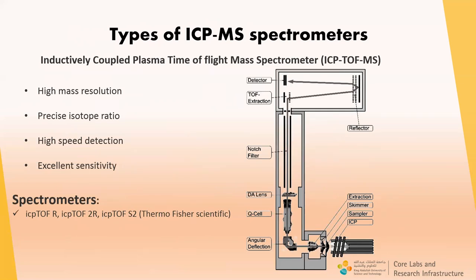Let me say a few words about inductively coupled plasma time-of-flight mass spectrometry. In the time-of-flight mass analyzer, the ion's mass-to-charge ratio is determined via a time-of-flight measurement. Ions are accelerated by an electric field so that all ions have the same kinetic energy but different velocities depending on mass-to-charge ratio; consequently, the time of flight depends on mass-to-charge ratio. Modern ICP-TOF-MS spectrometers combine ICP ion optics, collision reaction cell, and vacuum system of quadrupole spectrometers with an ion filter, additional ion optics, and orthogonal acceleration analyzer, providing high mass resolution, precise isotope ratios, high-speed detection, and excellent sensitivity.